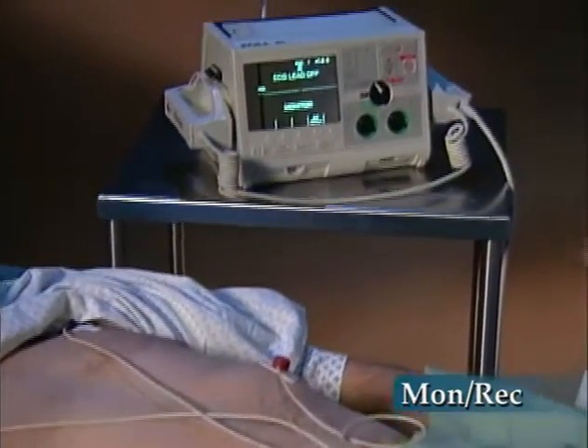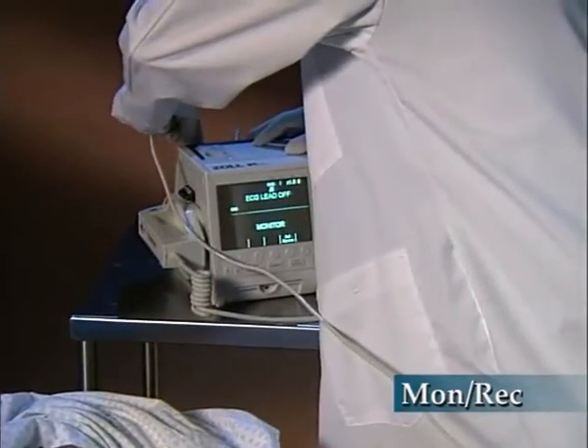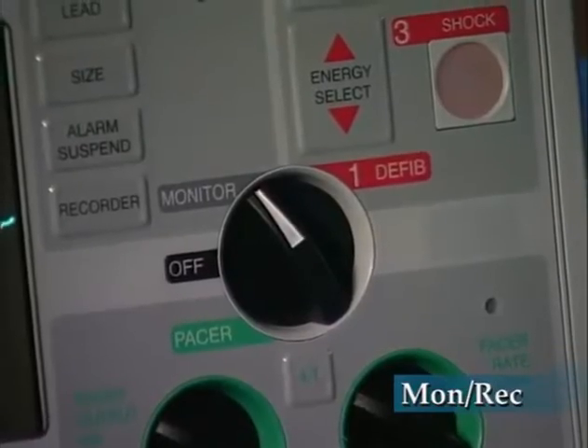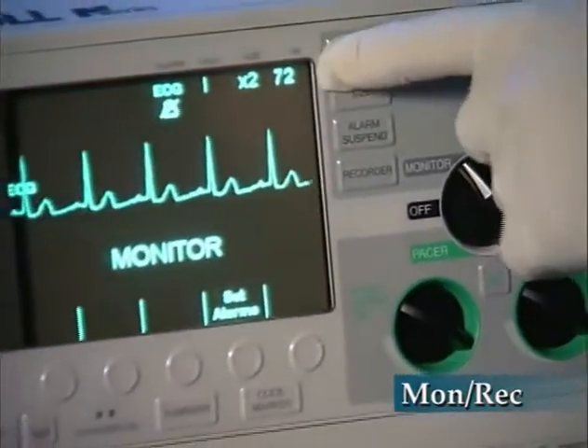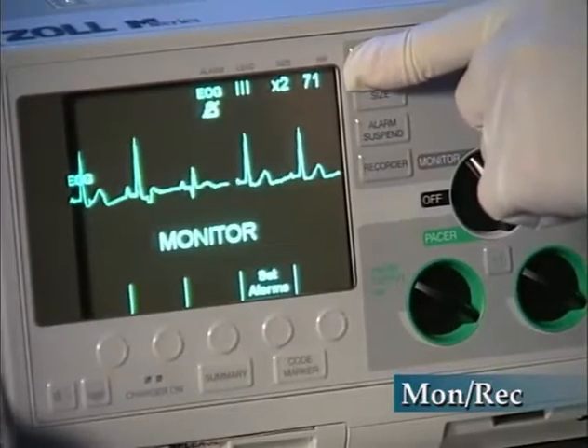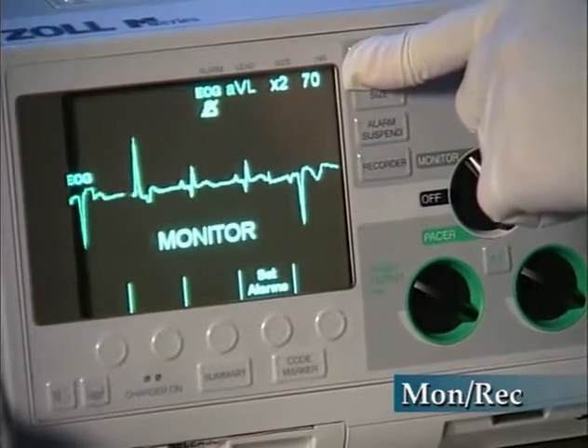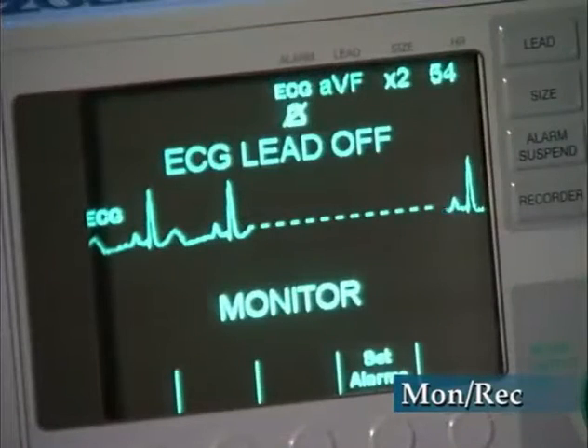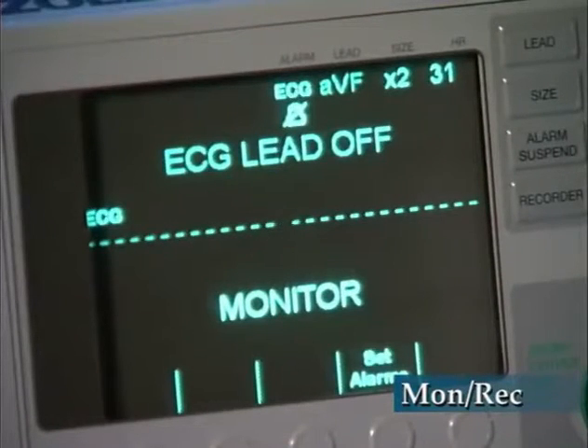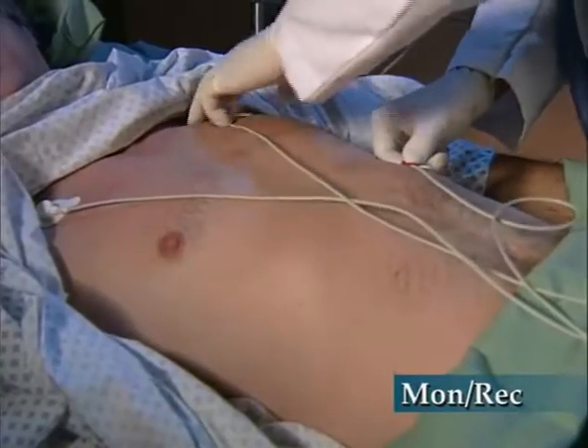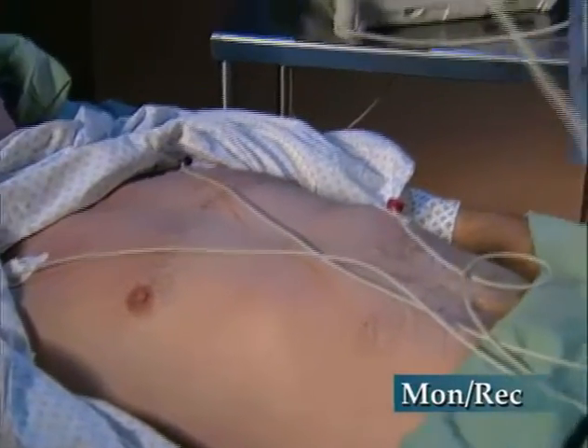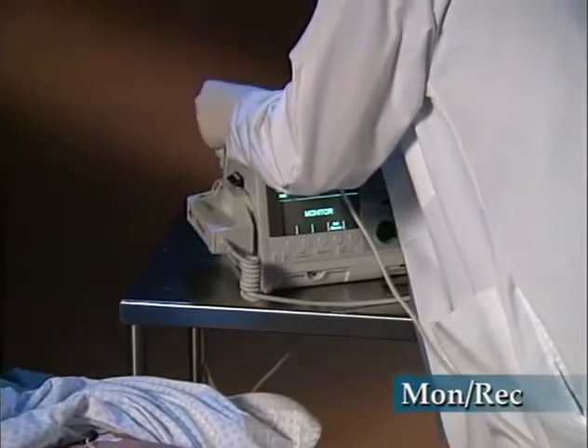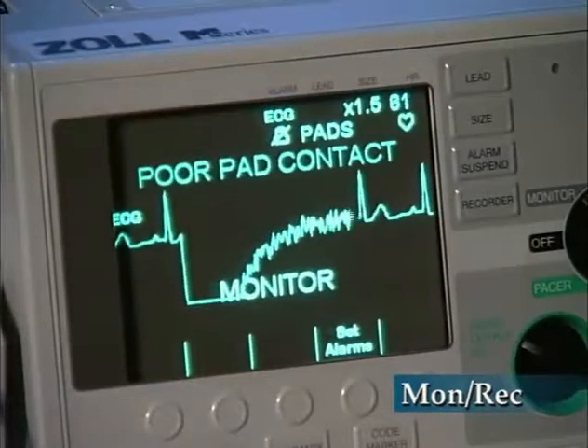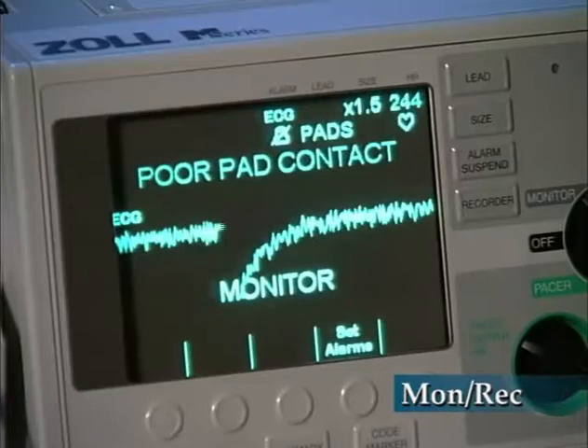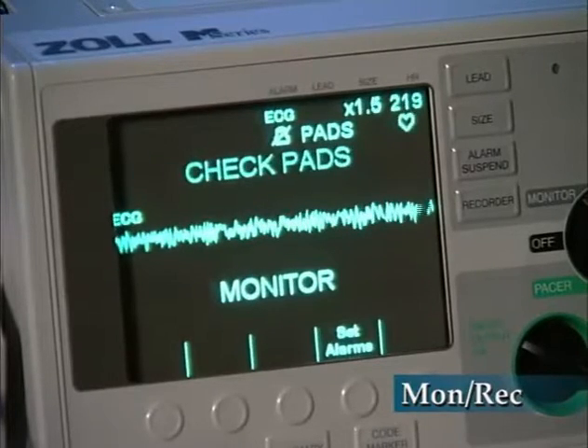Plug the patient cable into the ECG input connector at the back of the unit. The selector switch should be in the monitor or on position. Press the lead button until the desired lead is selected. If the ECG lead-off message appears, inspect the ECG electrodes, lead wires, and connections. If the check pads or poor pad contact message appears, inspect the MFE pads, cable, and connections.